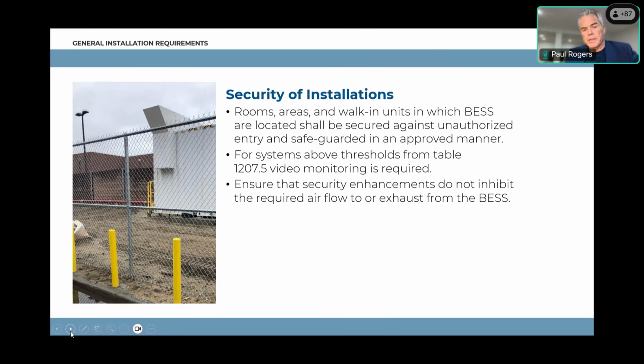We also want to make sure these do not inhibit any required airflow. As Bill mentioned, one of the things they have is making sure we can pull gases out, and we want to make sure that fan exhaust isn't blocked by anything outside. Some of these things may be on the rooftop, so we need to make sure nothing is obstructing the pull of those gases, to reduce any concentration buildup on the inside and prevent any type of explosion from taking place.